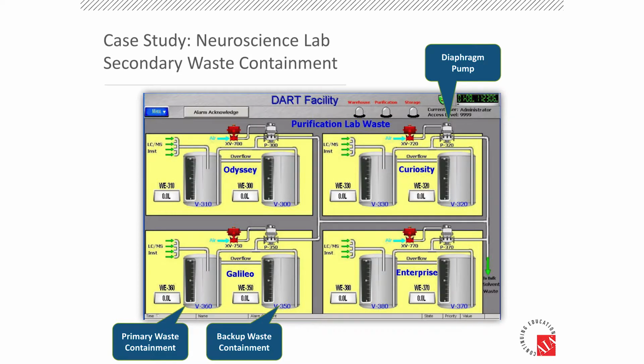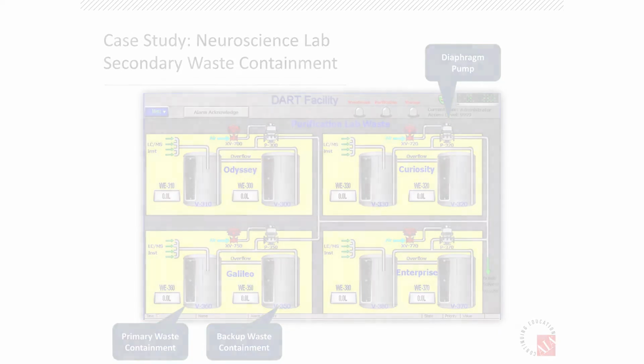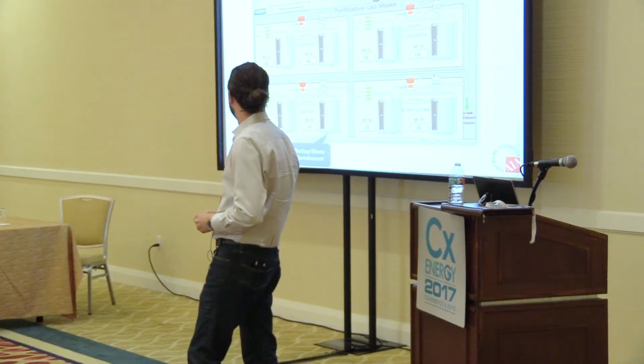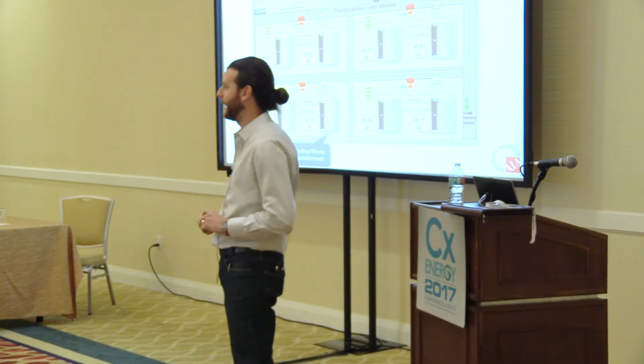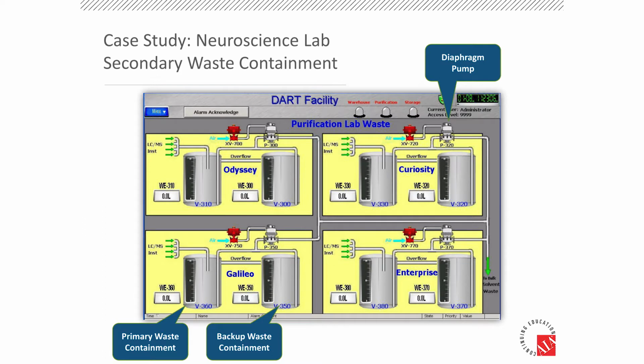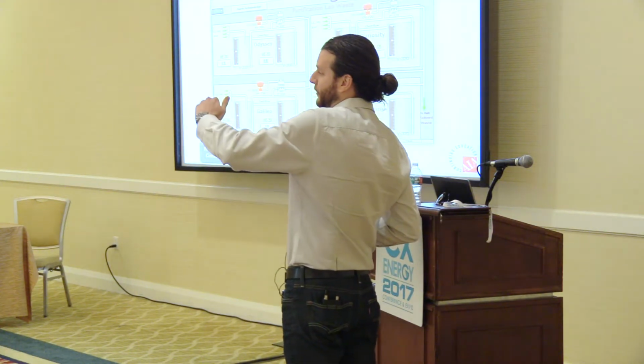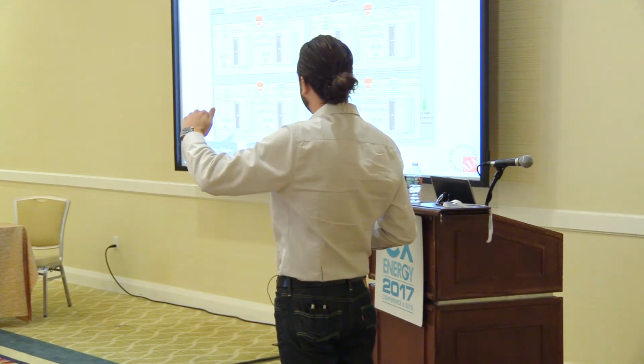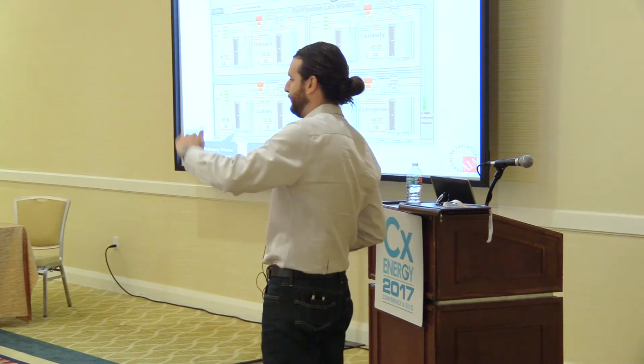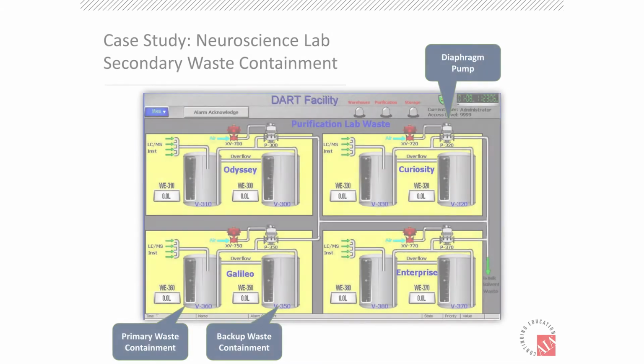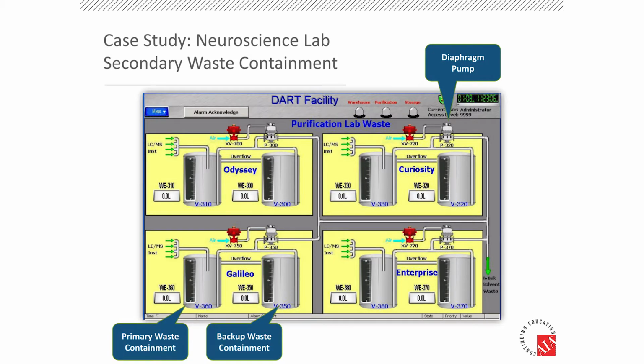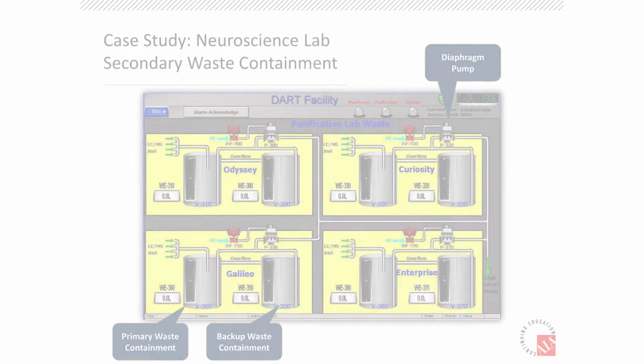So after the HPLCs use that solvent, it's dirty, it's nasty, we've got to get it out of there. They have their own internal pumping system that pumps that solvent into some waste tanks that are located in biosafety cabinets within the lab. Similarly, they have a primary and secondary tank. The primary tank is used to fill. Once that fill gets up to a high level, the control system says, okay, I've got to kick on this diaphragm pump, and the diaphragm pump pumps the waste back to the main solvent waste system. The reason diaphragm pumps are used is these are intrinsically safe biosafety cabinets. You can't have any electricity in there. It's all pneumatically driven, and that's very important based on the chemistry makeup.